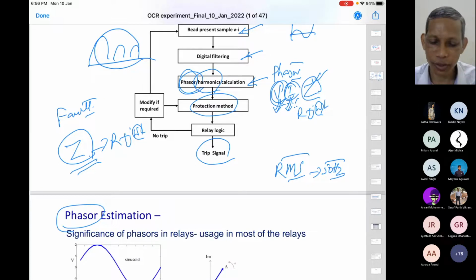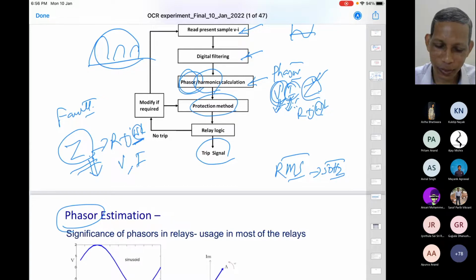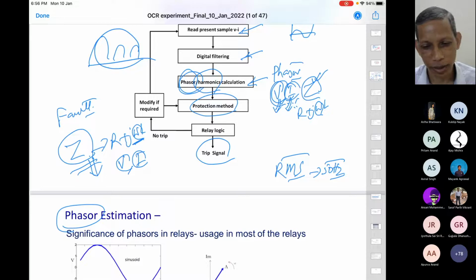Now the relay, the protection system, is designed based on impedance. For this impedance, how will we find it? Using voltage and current. Which voltage and current? This is fundamental, meaning the corresponding voltage and current should also be fundamental, because during a fault it goes through a transition. So there is transient voltage and current, and they are distorted, not perfectly sinusoidal like in a normal situation.